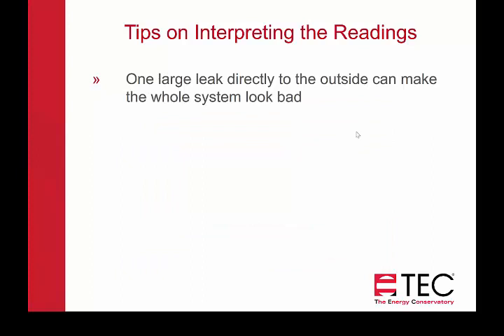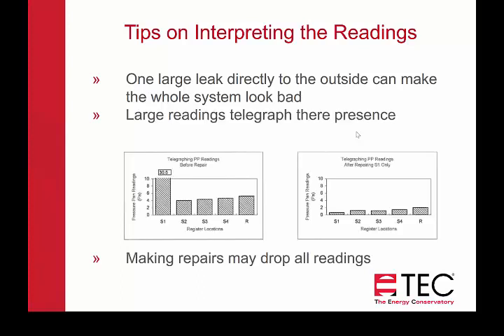Again, one leak directly to the outside can make the whole system look bad. In this example, we've got one supply register where we're getting a reading of 30.6 pascals, and it telegraphs through the other ones — all of our other readings are between four and five. It looks like we've got a lot of potential leakage, but they made the repairs on that one duct and all of the pressures throughout the whole system dropped. That's one thing to look for: is there just one really high number that's dominant? If so, seal that one and then take your measurements again before going after other leaks.